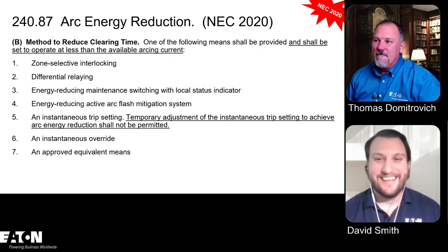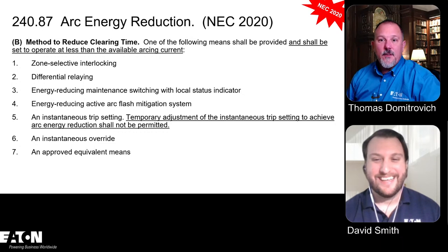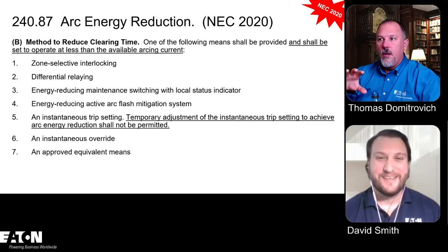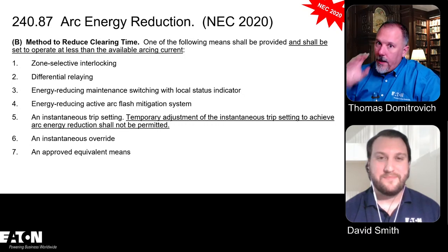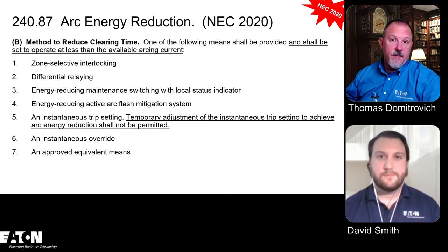I love it. Zone selective interlocking, differential relaying. Now, we're going to talk about these in a certain order. I rarely see differential relaying on 480 volt systems or 208 volt systems. Differential relaying, in my experience, has been in medium voltage applications.